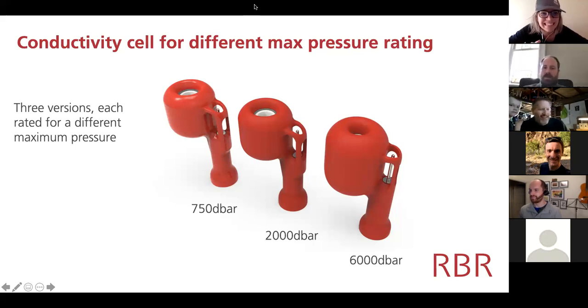That's totally not allowed. But on that note, is it only the center of the conductivity cell that would need to be kept clear? Really, the whole thing needs to be kept free and clear, right? That's right. So you need to illuminate the whole thing. But we use this 80-20 rule of life, really, and 80-20 also happens to be about the right proportions for the RBR conductivity cell. 80% of the measurement is taken inside the cell, 20% is around the outside. So if you can keep the inside clear, you've already fixed 4/5 of the problem. The outside would be the last fifth. So yes, you would like to illuminate the whole thing, but even something would be better than nothing in those highly active areas. Cool.